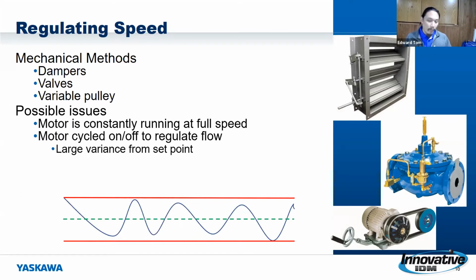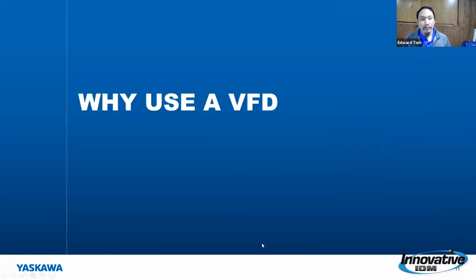Now, I'll go back to the Reeves drives, is that there was only so much speed control that we had on there. So you can only go so low when it came to the speed. So there are points where if you run to a certain point, you may find out that I can't get any slower. I'm actually putting out too much at this point, so I need to stop the machine at this moment. So that's what you may end up doing, just shutting off the machine and then restarting it, and then seeing that current coming up. So those are some of the things that you may run into.